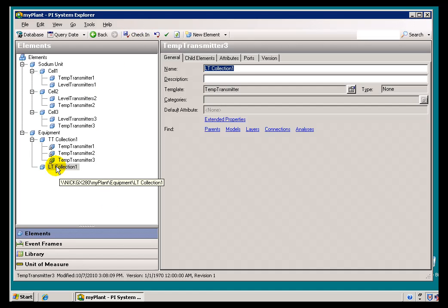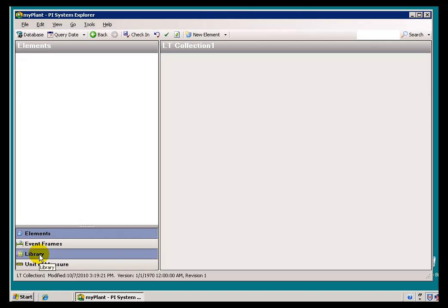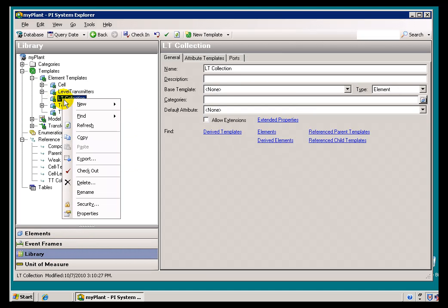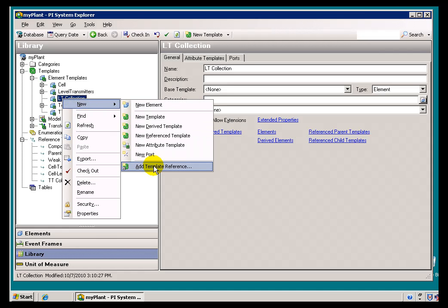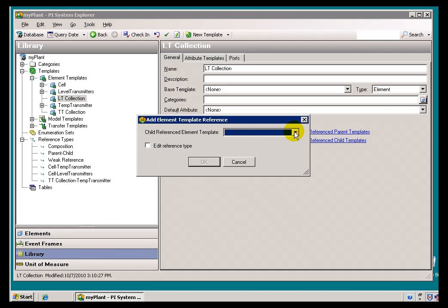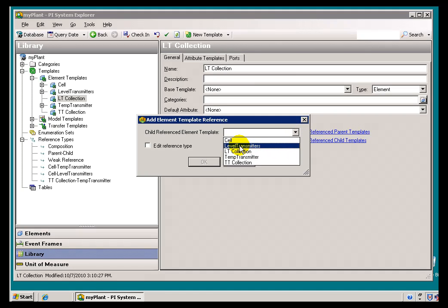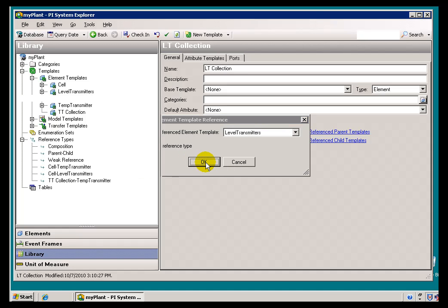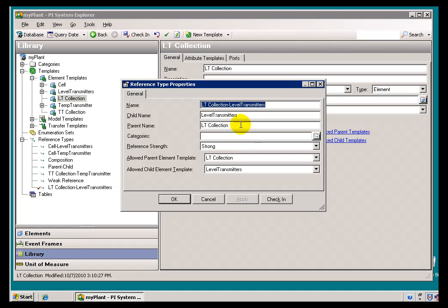Let's go back and do the same thing for our Level Transmitter Collection. For the Level Transmitter Collection, we want to create a new Reference Type — but this one is going to be a regular Strong Reference Type. We don't need this to be a Weak Reference Type. Because, remember, we can reuse those Level Transmitters; if we delete them from the tank or from the cell, we don't need to delete them from this list. So we'll add a New Template Reference. The Child Reference is going to be the Level Transmitters. We'll have the Default Strong Reference — and here's our Big Finish: a new Reference Type called Level Transmitter Collection to Level Transmitters, which is a Strong Reference Type with the Allowed Parents and Allowed Children defined.